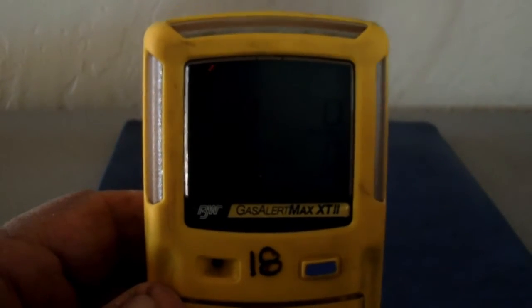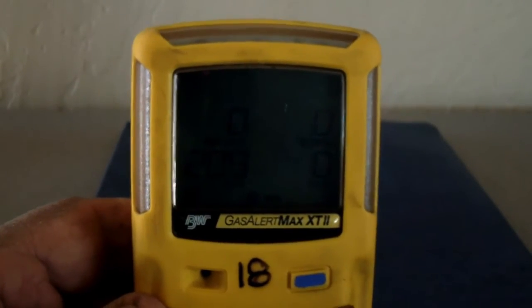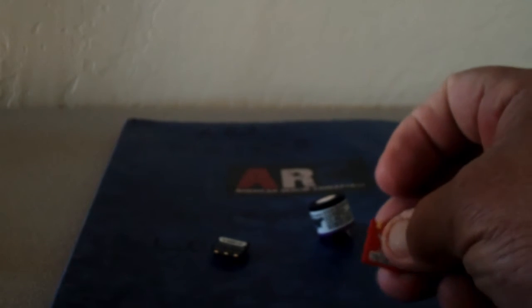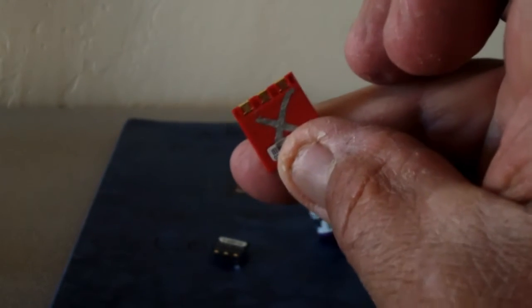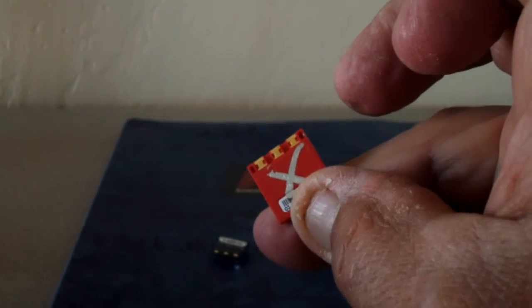I've got some Cal gas with me. I'm going to move this out of the way and show you the Cal gas. Before I do that, let me show you the sensors. We got a hydrogen sulfide sensor right here that just plugs in. We've got a carbon monoxide sensor right there. You can see they just plug right in to the machine. I put an X on it so I know that they've been used and are no longer any good.